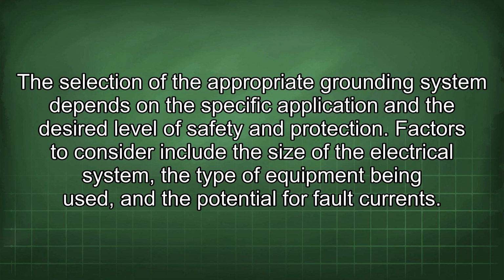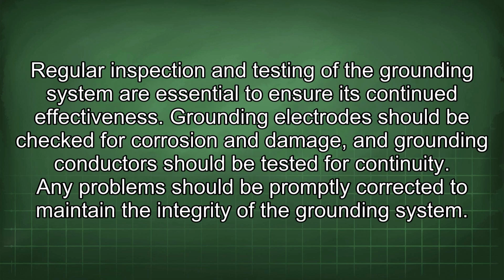Factors to consider include the size of the electrical system, the type of equipment being used, and the potential for fault currents. Regular inspection and testing of the grounding system are essential to ensure its continued effectiveness. Grounding electrodes should be checked for corrosion and damage, and grounding conductors should be tested for continuity. Any problems should be promptly corrected to maintain the integrity of the grounding system.